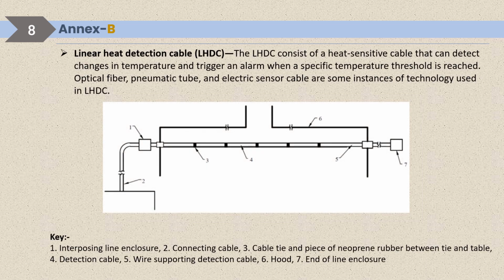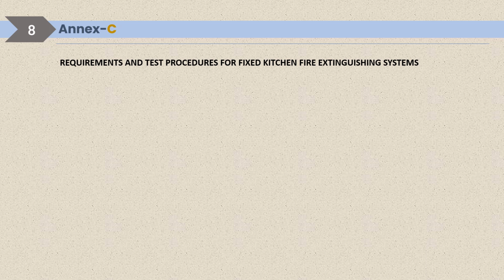Next is linear heat detection cable. The linear heat detection cable consists of a heat sensitive cable that can detect changes in temperature and trigger an alarm when a specific temperature threshold is reached. Optical fiber, pneumatic tube and electrical sensor cables are some instances of technology used in linear heat detection cable. So these are the few detection methods that actuate the fire suppression system. Annexure C talks about the test procedure of kitchen fire extinguishing systems. I have not included it here. If you are interested, you can see Annexure C of this standard.